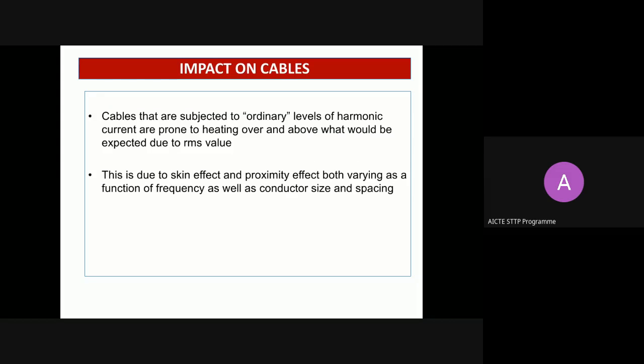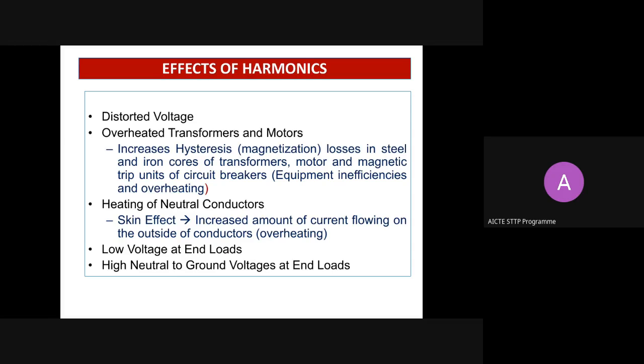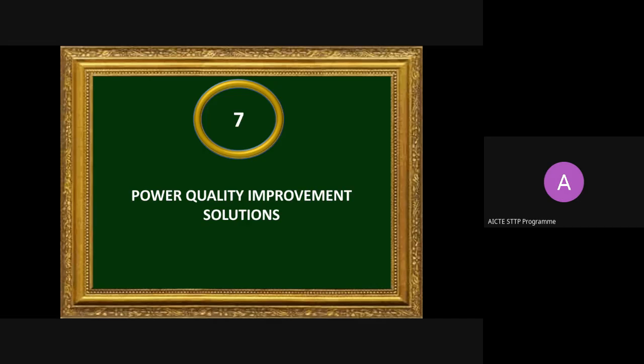And then cables. Cables subjected to even ordinary levels of harmonic current are prone to heating over and above what would be expected from RMS. With more harmonic current, cable burning will naturally happen. That is the impact on the cable. So, put together, non-linear loads cause distorted voltage at the point of common coupling, overheated transformers and motors, heating of neutral conductors, low voltage at loads, and high neutral to ground voltage at loads. These are some of the common problems prevalent in most places because of poor power quality, or the effects of harmonics. Okay, next: what are the solutions we are generally following at present for improving power quality?